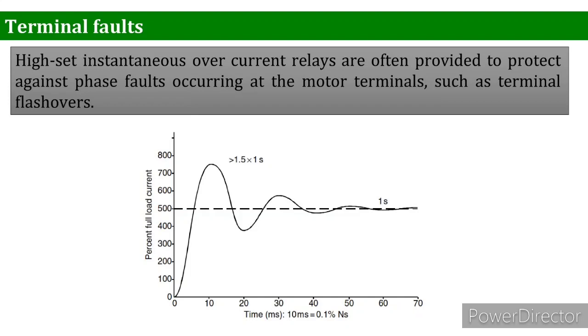Terminal faults. As we know, high set instantaneous overcurrent relays are often provided to protect against phase faults occurring at the motor terminal, such as terminal flashovers. Care must be taken when setting these units to ensure that they do not operate on the initial peak of the motor starting current, which can be 2.5 times the steady state RMS current.